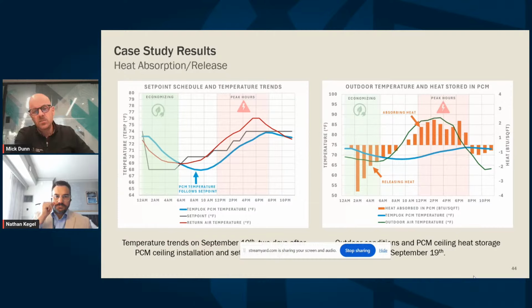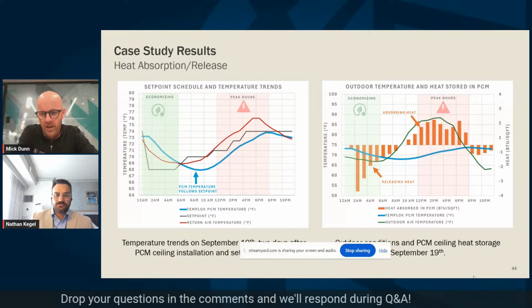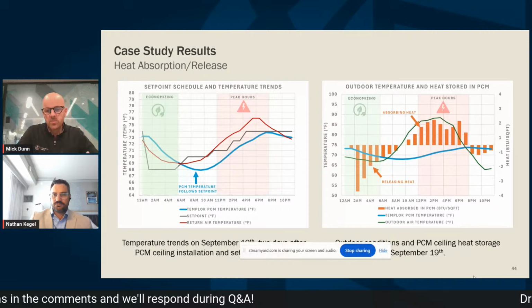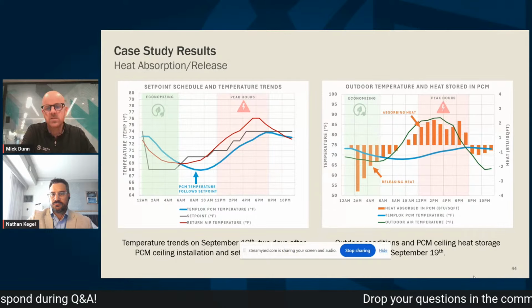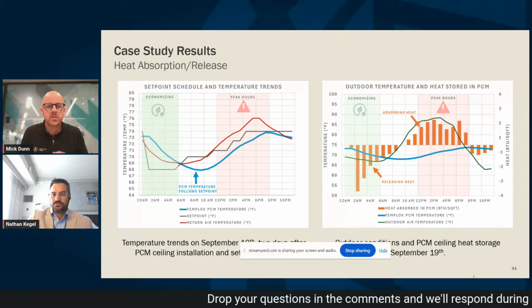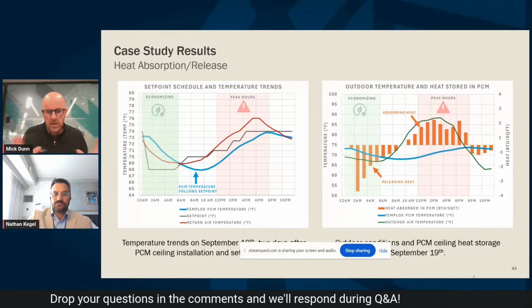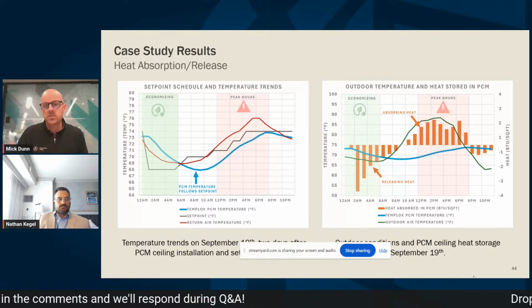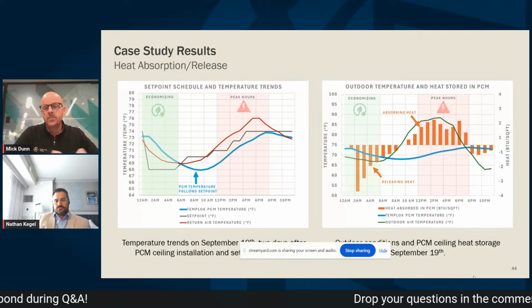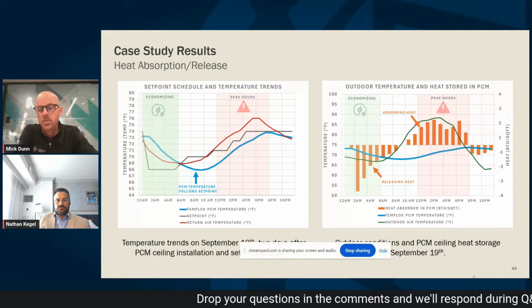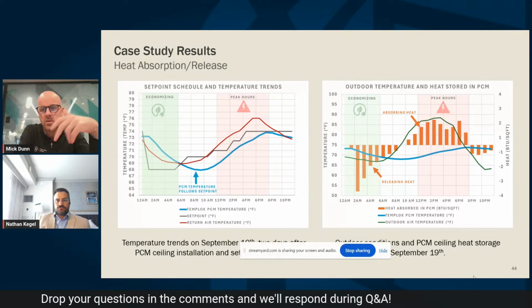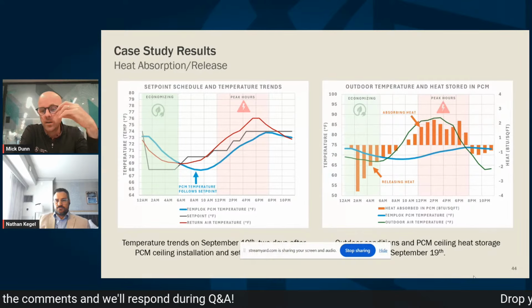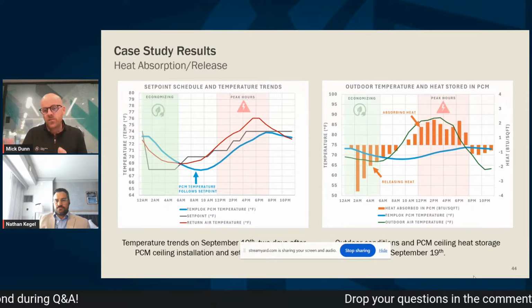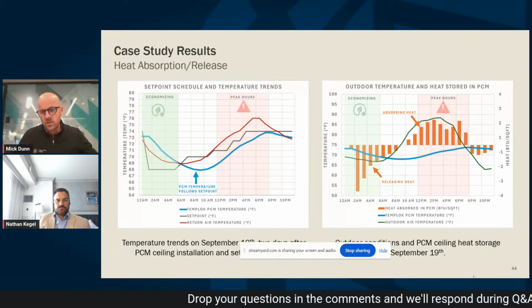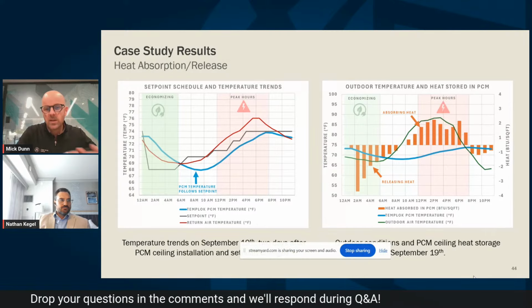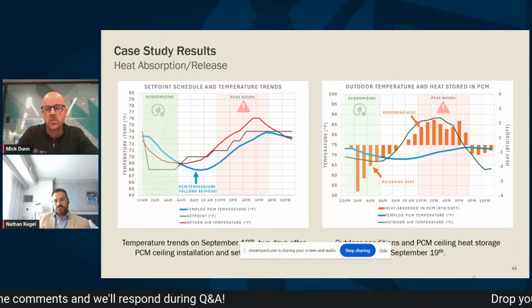And so what we saw in the absorption and release, both in the heating coil and the measurement of energy that we're seeing on the tile itself, was a large release of heat happening in the first couple hours of that ventilation. So most of our recharge is happening within about 1 to 2 hours of economizer cooling. Now our ceiling's charged, but we're just making sure through the rest of the evening. And then as temperatures rise throughout the day, which is what we're seeing on the right side there, we're seeing essentially that inflection point happening as the building is occupied and begins to go above 71, 72 degrees. Now the ceiling begins to do its work. Now it begins to absorb energy, and we're concentrating that further in the afternoon, pushing all that energy across the afternoon during the peak hours, where we're assuming is the most expensive and least efficient time of day to be doing cooling.